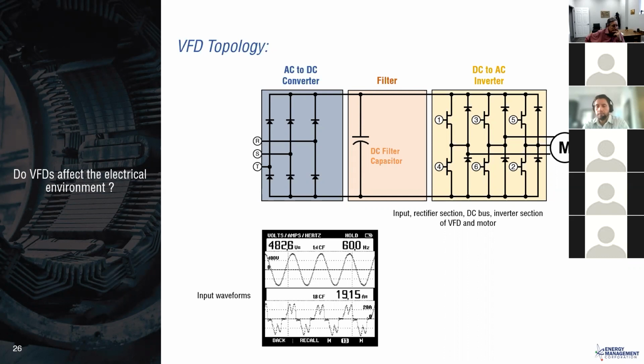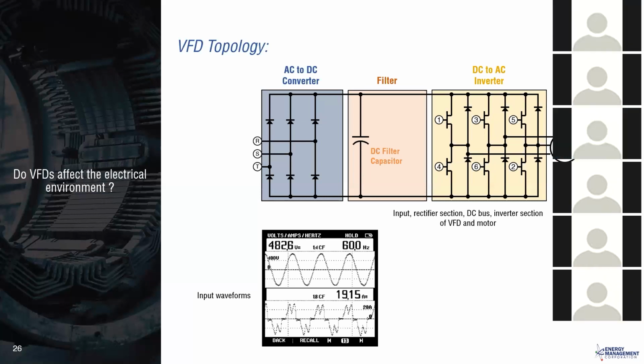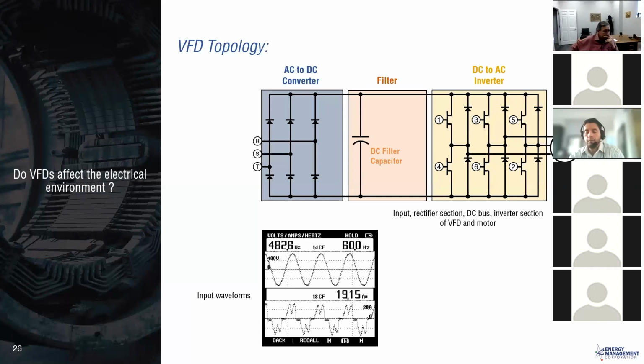So here you can see that we have a graph where we have voltage and current of a typical 6-pulse VFD input waveform with load on it. That's how the current waveform looks. This topology reminds us of UPS systems, where we do have similar sections of rectifier, inverter, and DC bus, but the DC bus charges the batteries. I want to say here that most variable frequency drives and UPS systems utilize a 6-pulse rectifier configuration. That is typically the seen configuration, but we do have different configurations too. When we have such a configuration, we see solid state power devices, of course, diodes typically, and diodes during the rectification process, because of commutation notching, create ringing frequencies, which I call harmonics.